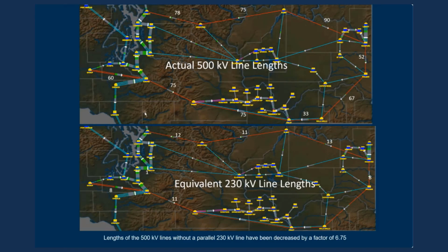Now let's look at the 500 kV lines. We'll start out with just looking at those lines where we have a single circuit between 2 major substations. We'll defer on looking at the cases where we have a 500 kV line in parallel with a 230. We take the single circuit 500 kV lines, and we divide them by a factor of 6.75. So for example, the 75-mile line between Wenatchee and Elma is equivalent to 11 miles of 230 kV line, because we divide the 75 by 6.75. So we know that the electrical distance between two stations with a 500 kV line is much shorter than if that was a 230 kV line. So we're taking that concept that we often talk about and actually putting it in terms of numbers.